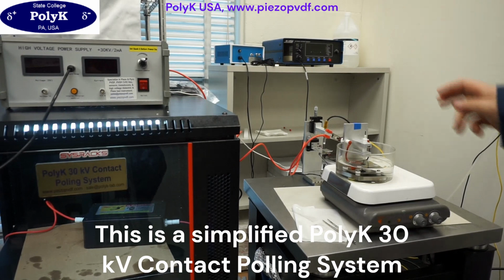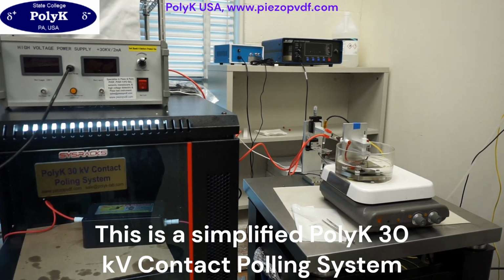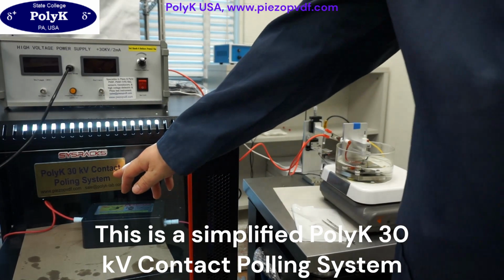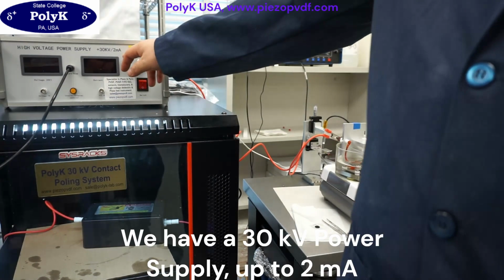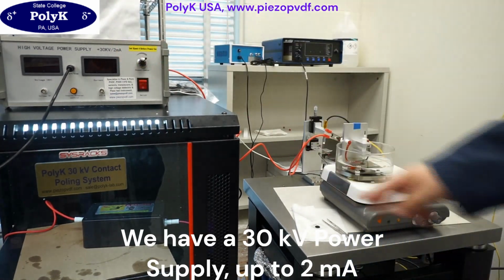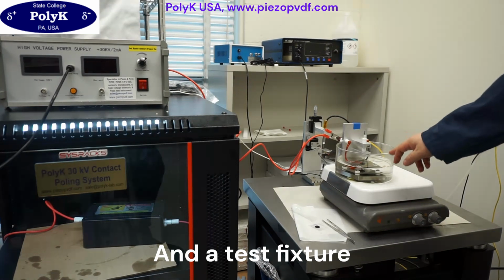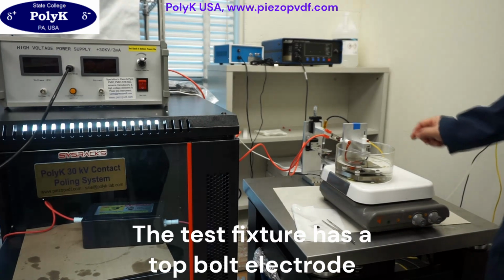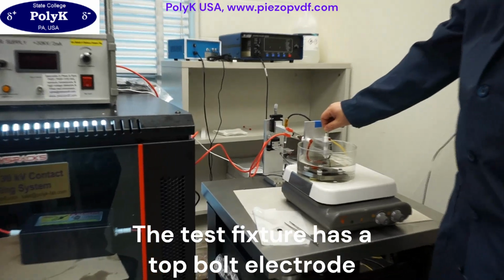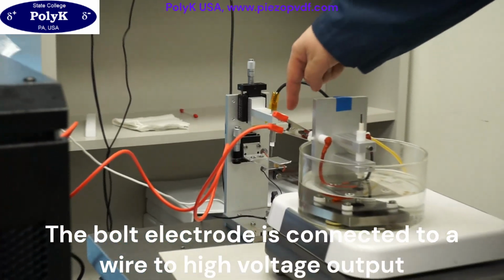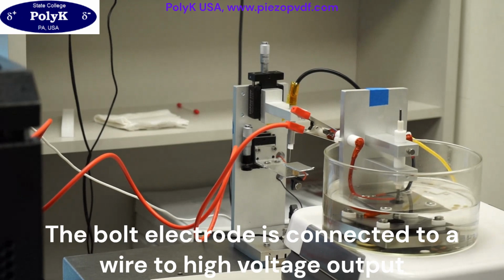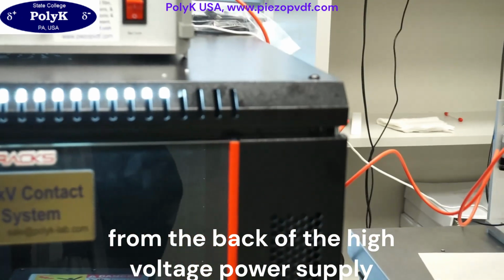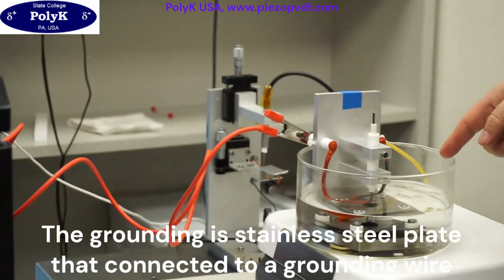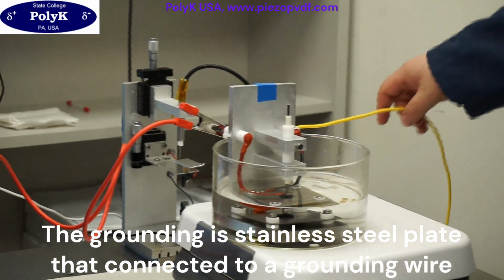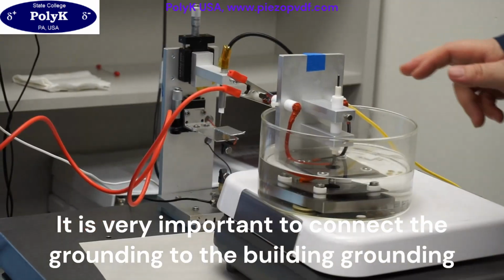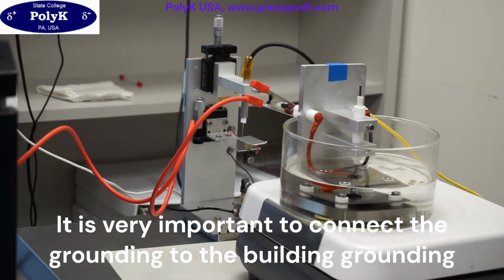Okay, so this is a simplified version of the PolyK 30 kV contact poling system. We have a 30 kV power supply up to 2 milliamp and a test fixture. The test fixture has a top ball electrode. The ball electrode is connected by a wire to the high voltage output from the back of the high voltage power supply. The grounding is a stainless steel plate that's connected to the grounding wire. Important: grounding to the building grounding.